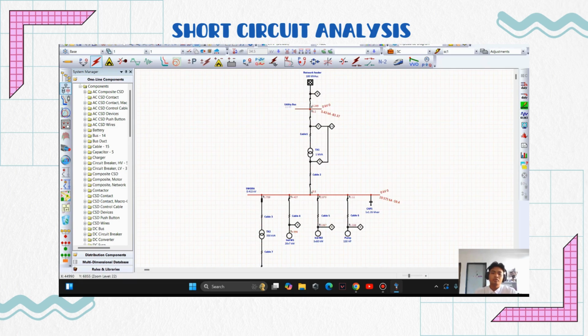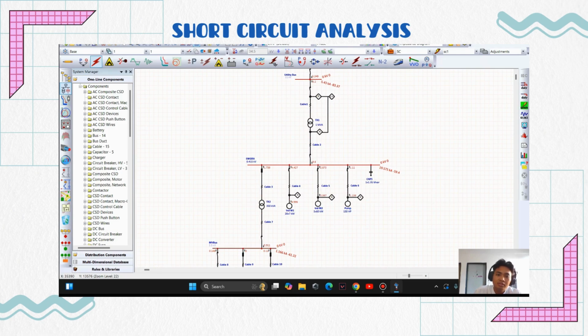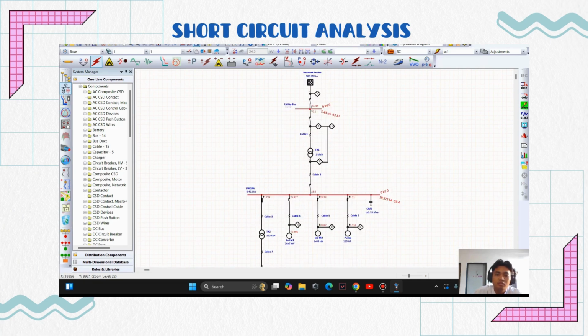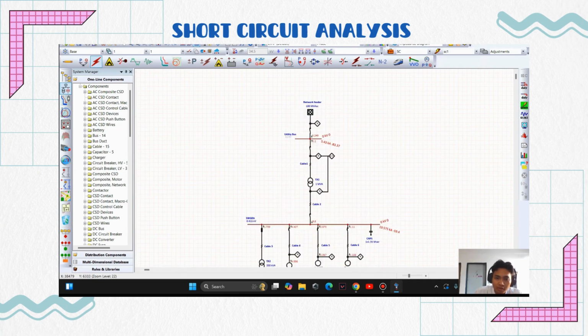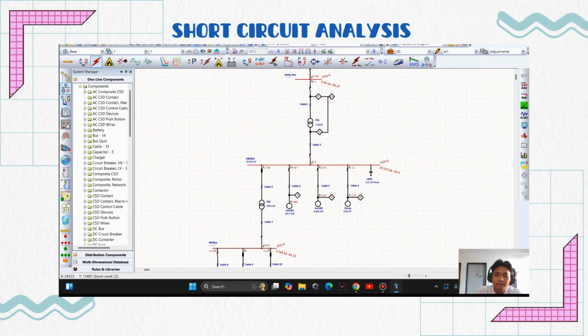From here we can see that they have three short circuits, which are from the utility bus, SWGRA and MV bus. Firstly, the utility bus at 11 kV has 5.43 kA. So this is the fault current for the utility bus. Second is the SWGRA, which has the largest and the highest fault current.